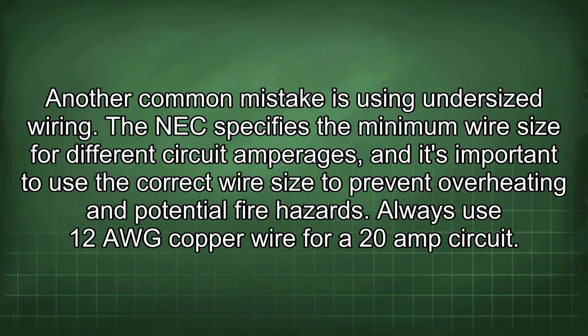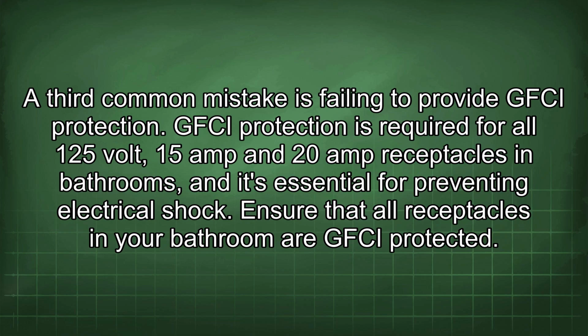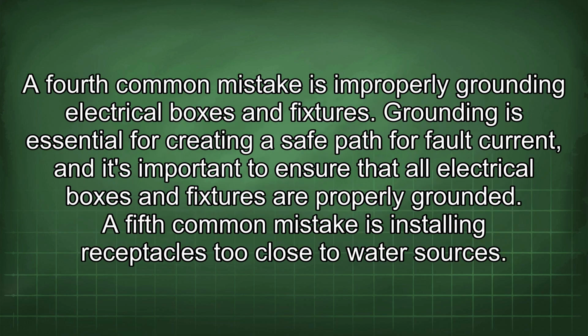Always use 12 AWG copper wire for a 20 amp circuit. A third common mistake is failing to provide GFCI protection. GFCI protection is required for all 125 volt, 15 amp and 20 amp receptacles in bathrooms, and it's essential for preventing electrical shock. Ensure that all receptacles in your bathroom are GFCI protected. A fourth common mistake is improperly grounding electrical boxes and fixtures. Grounding is essential for creating a safe path for fault current, and it's important to ensure that all electrical boxes and fixtures are properly grounded.